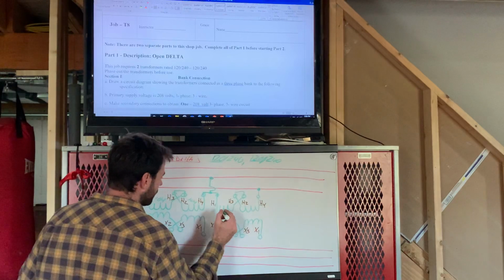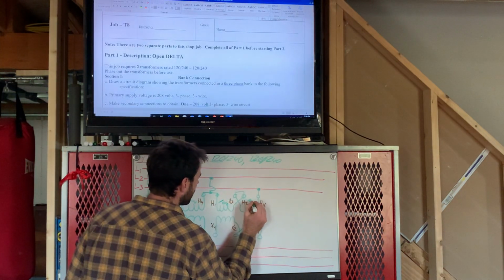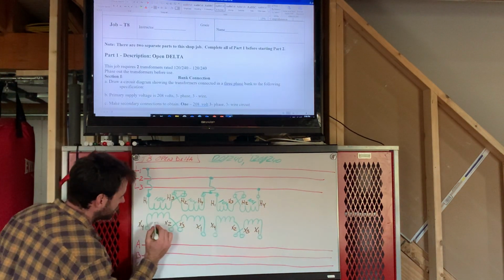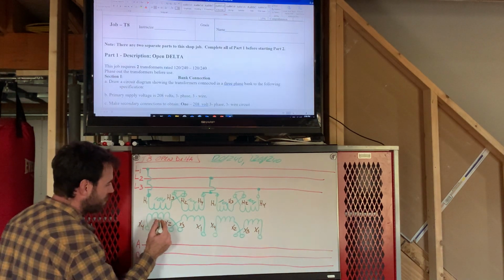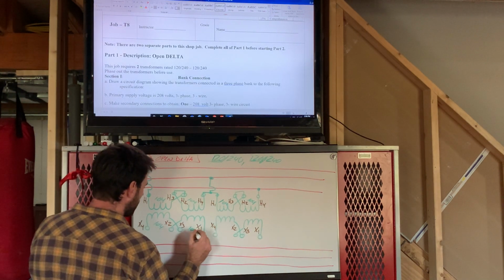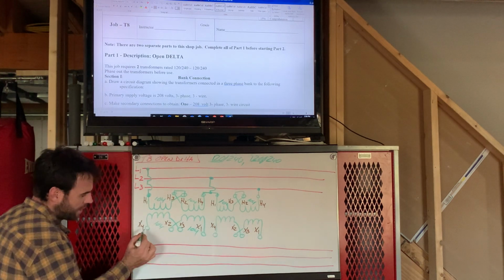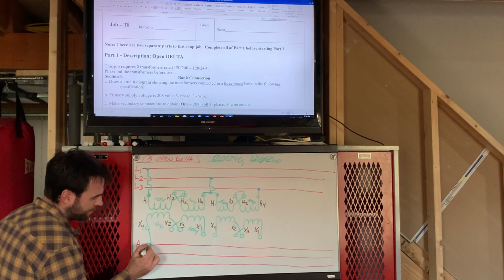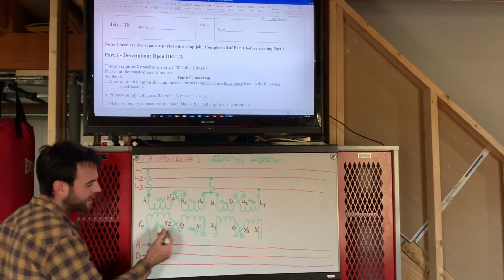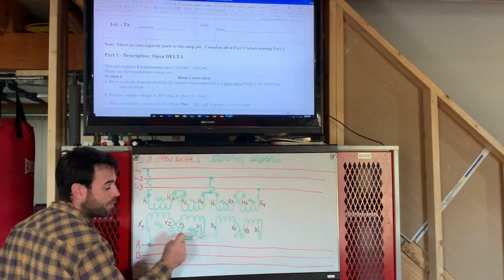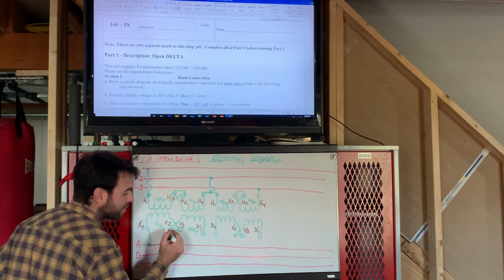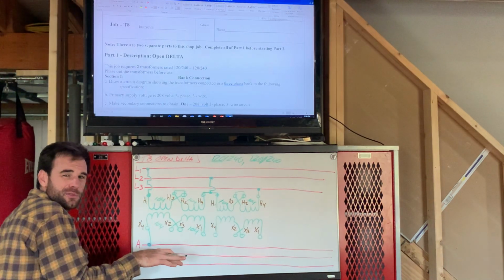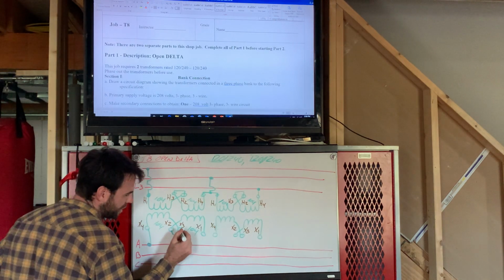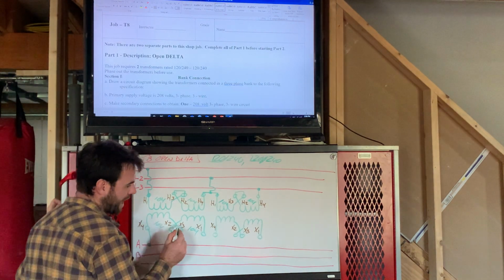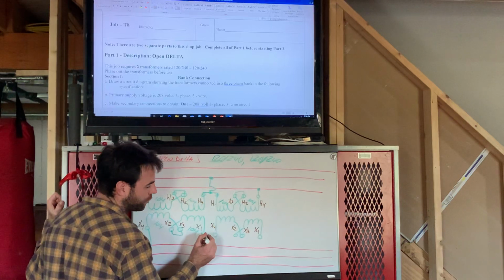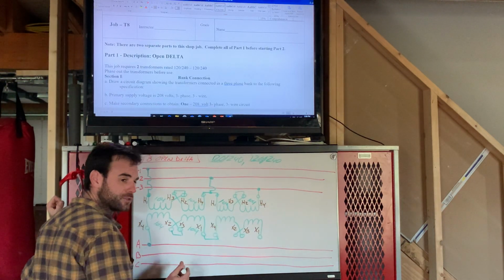We want to get 208 out. Well, if there's 104 here, 104 here, I'm going to induce 104 on this coil, so I'll induce 104 on this coil. X4 is going to make up the first part of phase A. Again, we're going to put these in series because we want to get 208 coming out. So if we put these in parallel, we would keep the 104 constant. We don't want to do that. We want to get 208 out, so we put these in series. X2 to X3. Then we're going to jump X1 of transformer 1 to X4 of transformer 2.